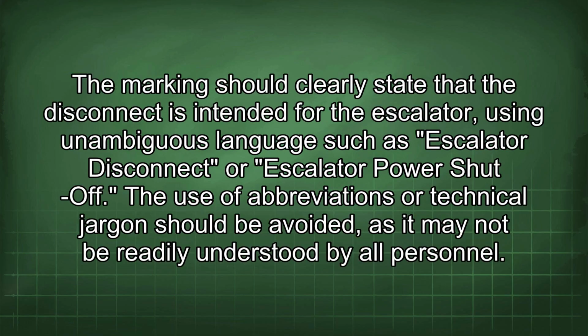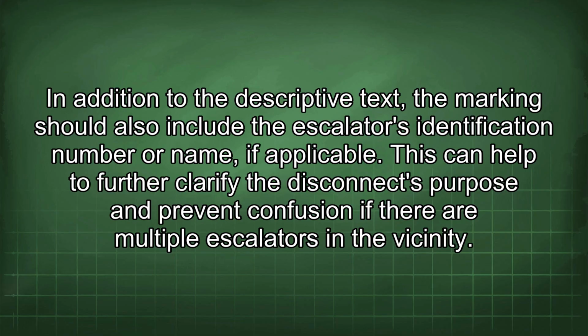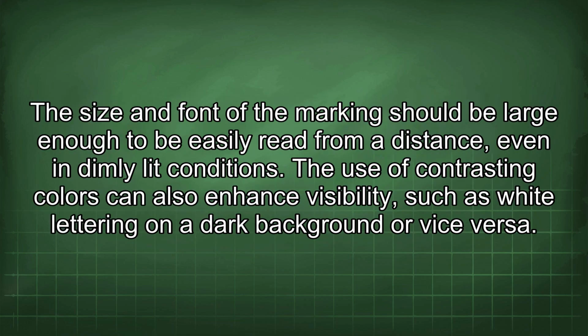The marking should clearly state that the disconnect is intended for the escalator, using unambiguous language such as "escalator disconnect" or "escalator power shut-off." The use of abbreviations or technical jargon should be avoided, as it may not be readily understood by all personnel. In addition to the descriptive text, the marking should also include the escalator's identification number or name, if applicable. This can help to further clarify the disconnect's purpose and prevent confusion if there are multiple escalators in the vicinity. The size and font of the marking should be large enough to be easily read from a distance, even in dimly lit conditions.